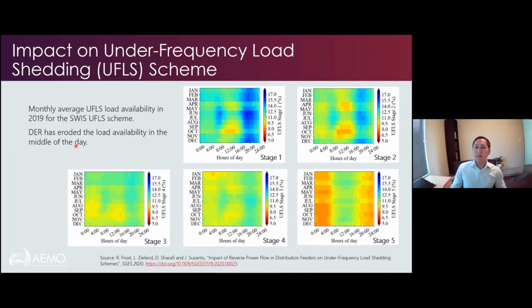So this is the effect DER is having on UFLS. DER has really eroded the availability of UFLS in the middle of the day. Our target here is 15%, so it should be blue. For stage 1, we'd want blue for the whole day, but in the middle of the day, especially in that October period, we're down at 9.5%, so we're really eroding the amount of UFLS available.